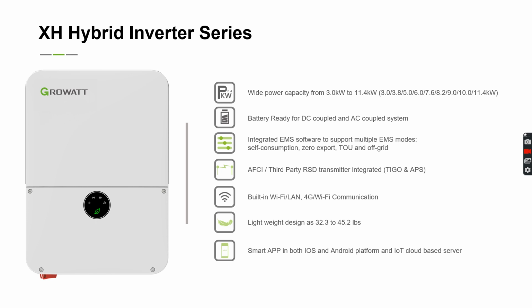The XH series hybrid inverter is a flexible inverter with Growatt offering a wide range of power capabilities from 3 kilowatts to 11.4 kilowatts. These hybrid inverters are ready for DC coupled and AC coupled systems and are integrated with an energy management software to support multiple EMS modes such as self-consumption, zero export, time of use, and off-grid modes. These inverters have built-in arc fault circuit interrupters for protection against short circuits, as well as built-in third-party RSD transmitters for compatibility with rapid shutdown systems.